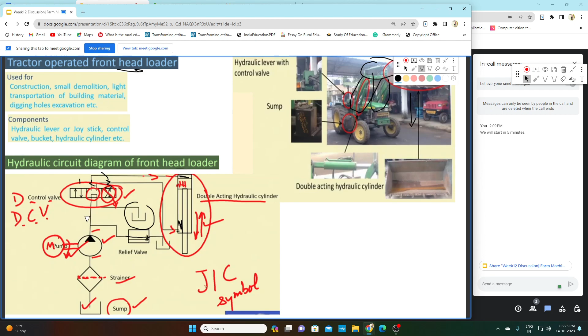Again I am telling, after the cracking pressure, the spring in the pressure relief valve will align with this line. The spring will be at this position. So all the flow in this line will be drained to this tank. By this, there will be no harm to the line as well as the direction control valve.